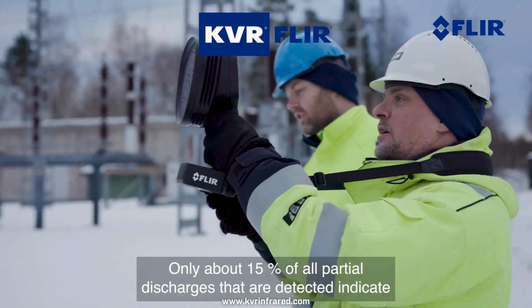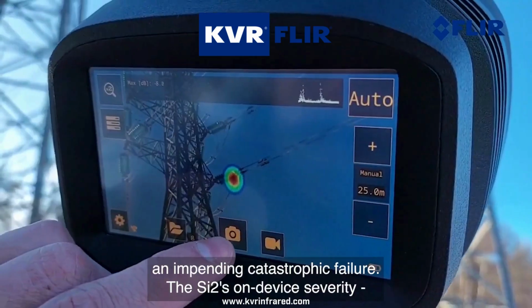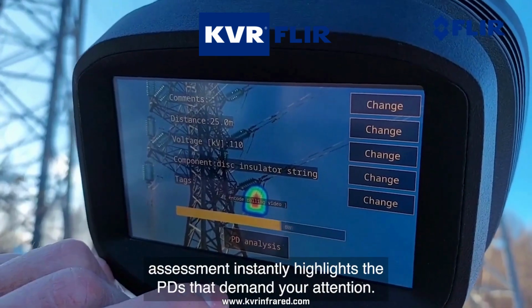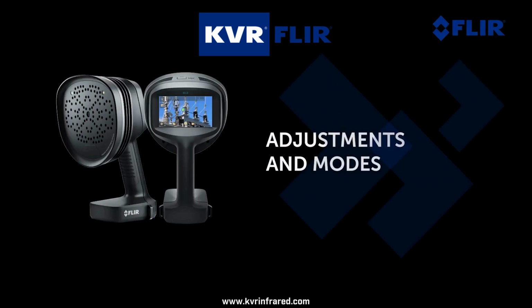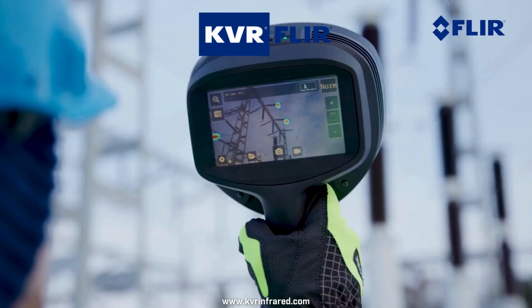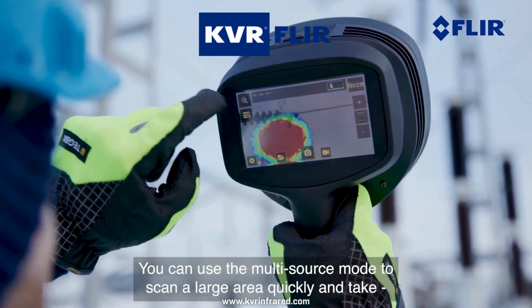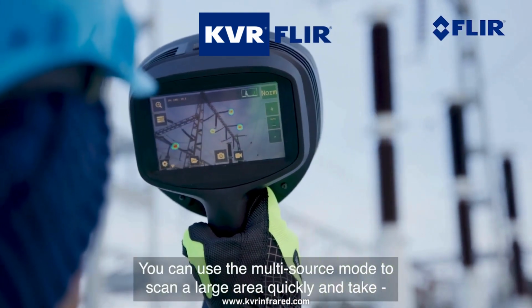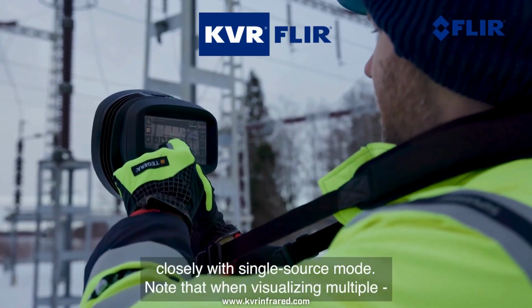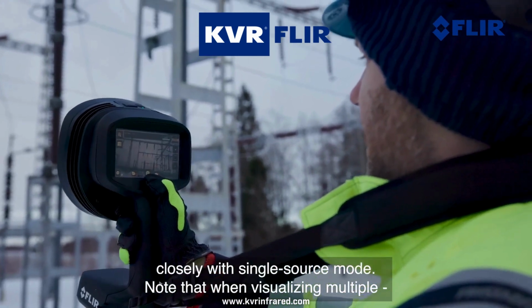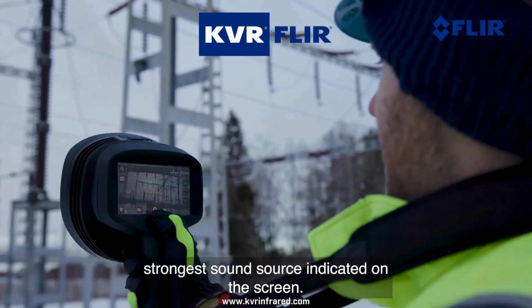Only about 15% of all partial discharges that are detected indicate an impending catastrophic failure. The Si2's on-device severity assessment instantly highlights the PDs that demand your attention. You can adjust screen brightness and zoom in and out with the camera. You can use the multi-source mode to scan a large area quickly and take note of several sound sources, which you can then inspect more closely with single source mode. Note that when visualizing multiple sources, the camera will only analyze the strongest sound source indicated on the screen.